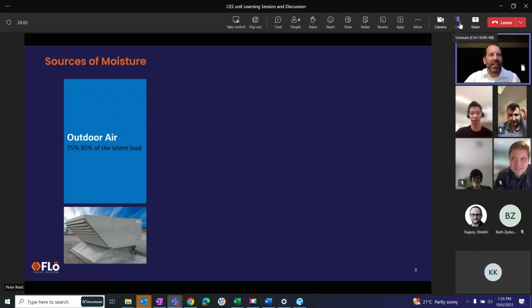It is 75% to 85% of what we call the latent load. Of course, you guys are all mechanical, so you know what that word means. It's our moisture load, and it's coming from the outside. So that's number one.